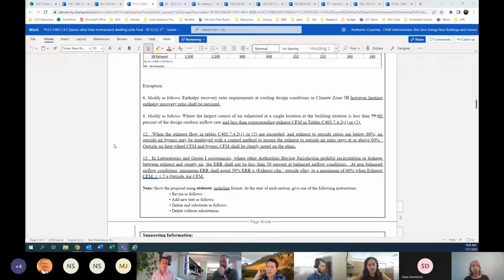I guess I'll jump in. I guess one of the challenges with the current, well, the way this is written, and the question I've asked from the beginning is, if you have a large exhaust, because IECC and ASHRAE solely look at the quantity of supply air and not the exhaust, and then determine it that way. So in this case, if we have an exhaust fan that exceeds one of the table values, the supply air is divided up amongst multiple RTUs or whatever, and so there's not as much at a single location. Would they still have to provide energy recovery?